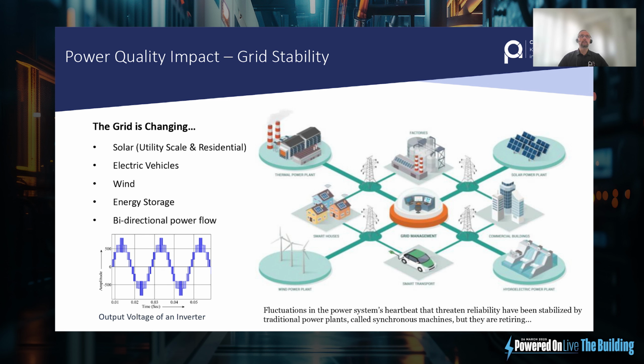But on top of that, we've got factories upgrading from a motor that may be spinning direct online, so it's connected straight into the grid via a contactor or star delta. It's been upgraded to soft starts and over time then to variable speed drives, which are the same technology that's inside an EV charger at the end of the day. And I would say in the last 20 years that has been a significant increase. So that, coupled with what's going on in the factory already, and then the addition of these other things that are going on, and higher switching frequencies, have an effect on the power system.